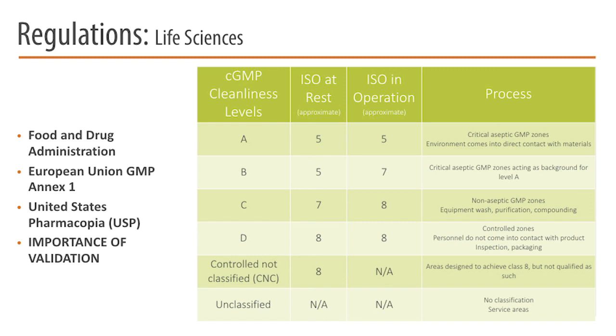Level A is typically a place where the environment will come into contact with the product, normally done in a biosafety cabinet or similar facility, whereas the background room would be a B and then C. As you progress from the locker rooms into deeper and deeper clean levels, you go through ante-rooms and do different gowning, etc. So there is a progression - you go from D to C to B, and you don't jump straight to, for instance, A.